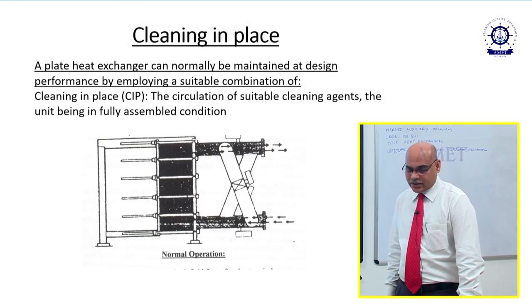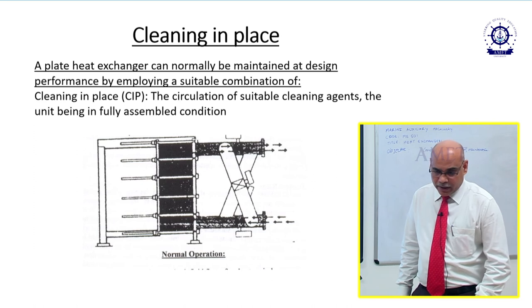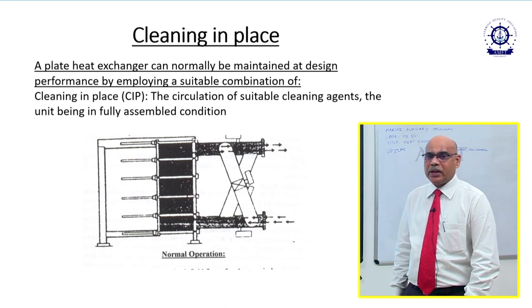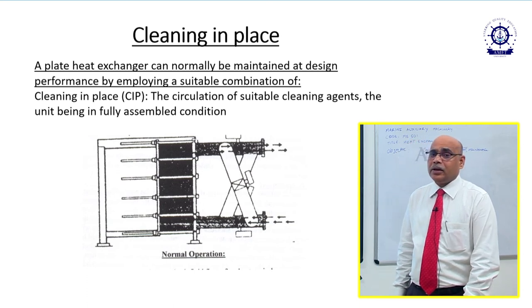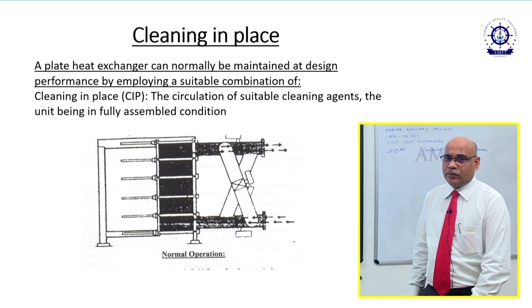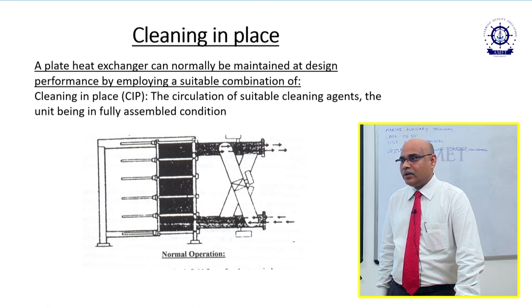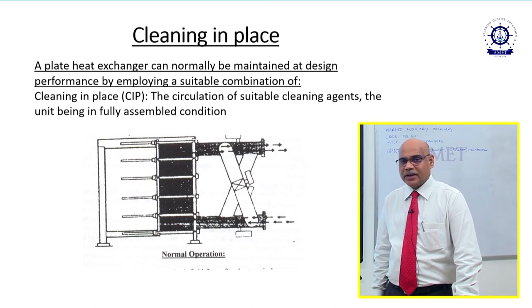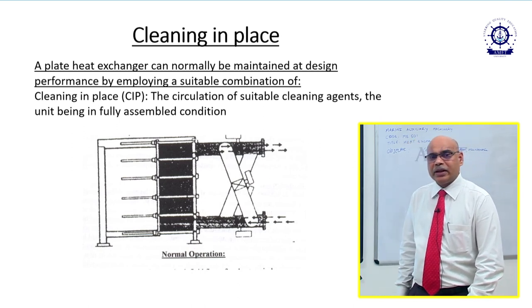There is one more method — cleaning in place (CIP). In some shipping companies, heat exchangers are maintained without opening, using a chemical cleaning method. Some companies specify that the heat exchanger has to be opened once in 10 years, and before that, at regular intervals it has to be chemically cleaned. This prevents gaskets or plates getting damaged by repeated dismantling.